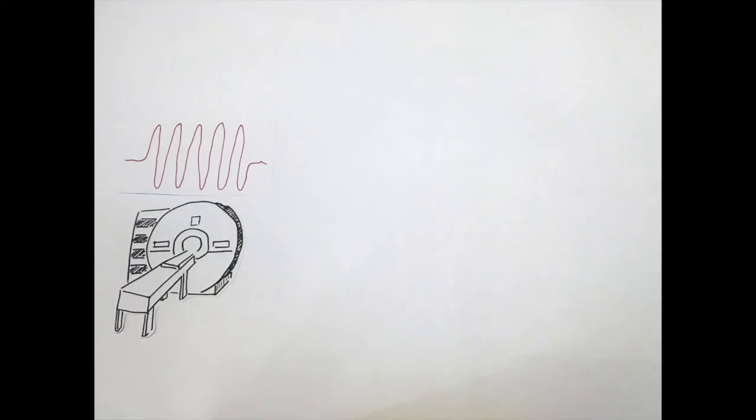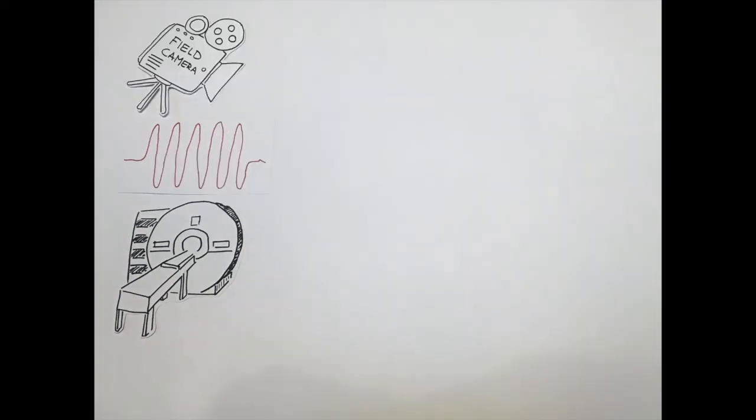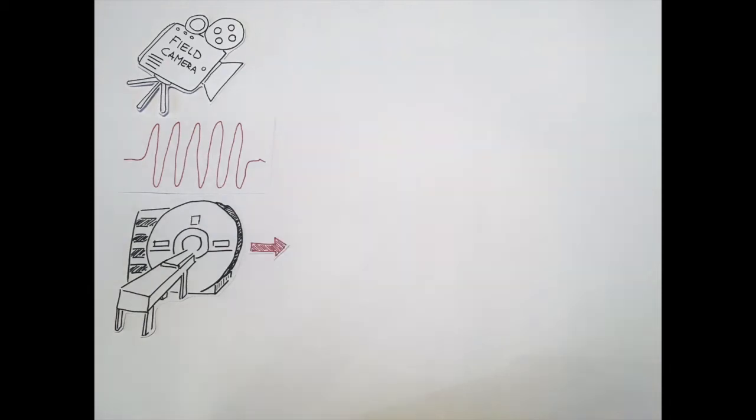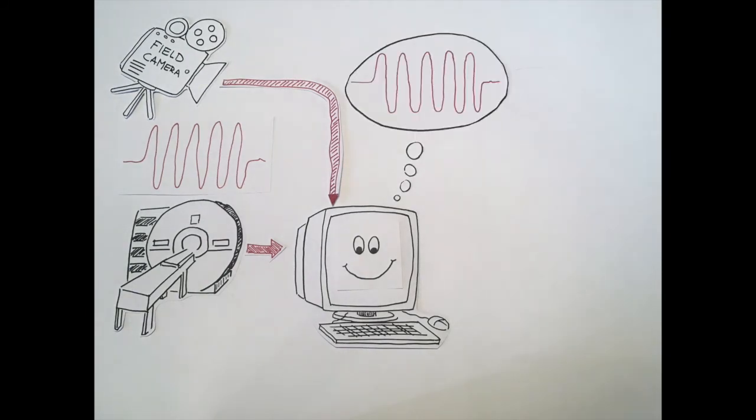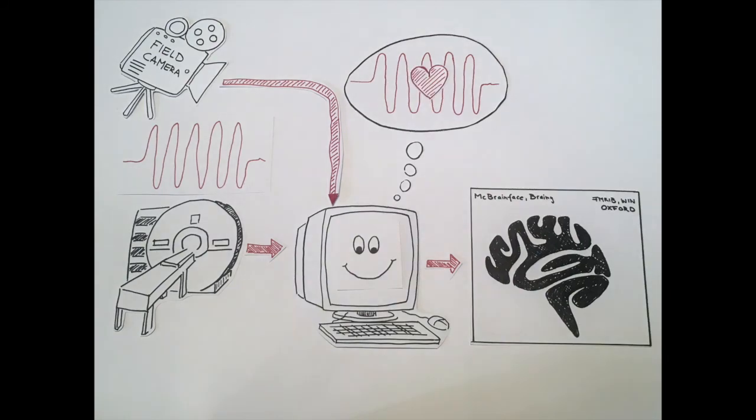One way to solve this problem is to use a field camera, which is a device that can measure the gradient magnetic fields. This information is then passed on to the image reconstruction computer, which allows it to correct for the imperfections and produce a high quality brain image.